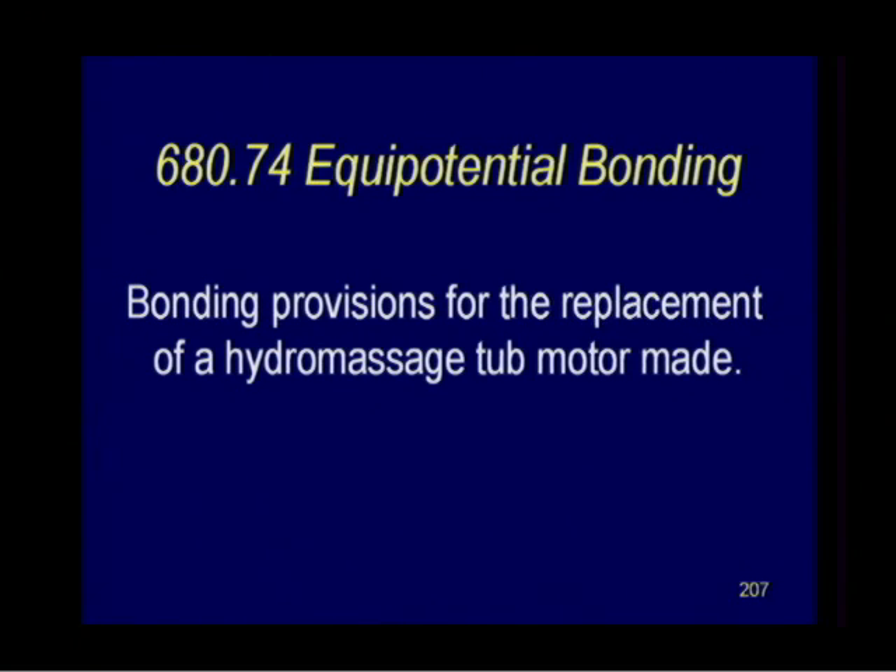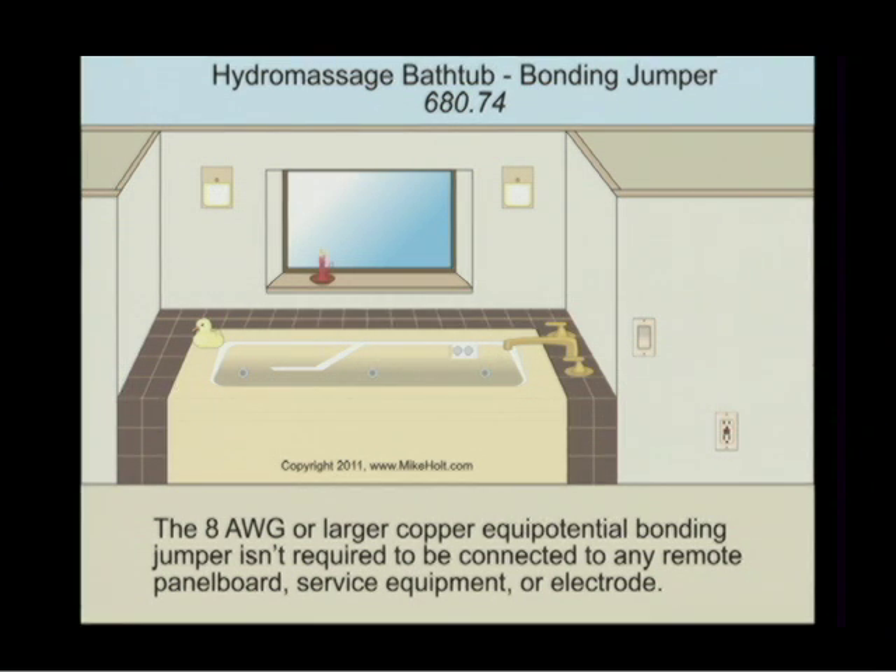NEC 680.74 covers equipotential bonding of the hydromassage bathtub. An 8 AWG or larger copper bonding conductor is not required to be connected to any remote panelboard, service equipment, or electrode. When you have a hydromassage bathtub, the bonding requirements confuse people — they think you're supposed to take the pump motor and run conductors everywhere, but the code usually tells you what you're supposed to do.